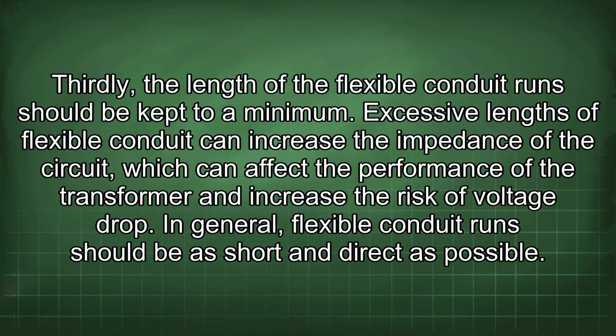Thirdly, the length of the flexible conduit run should be kept to a minimum. Excessive lengths of flexible conduit can increase the impedance of the circuit, which can affect the performance of the transformer and increase the risk of voltage drop. In general, flexible conduit runs should be as short and direct as possible.